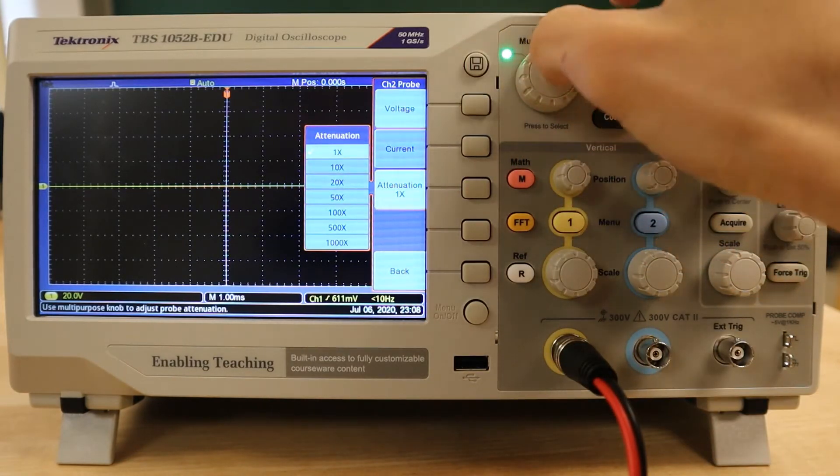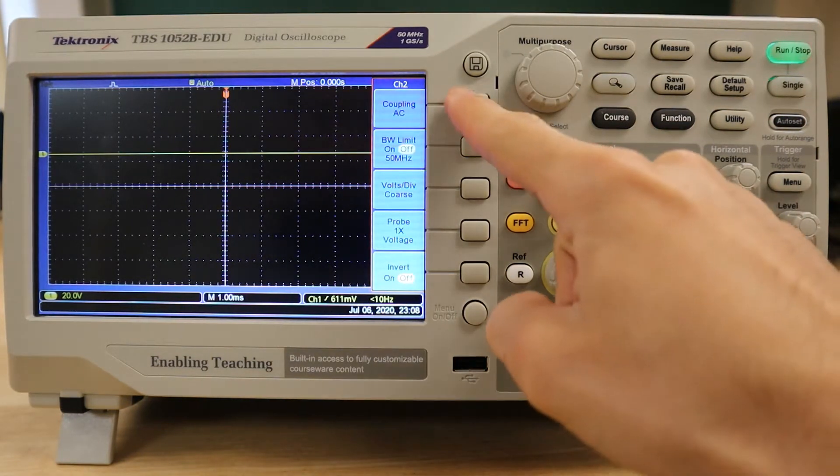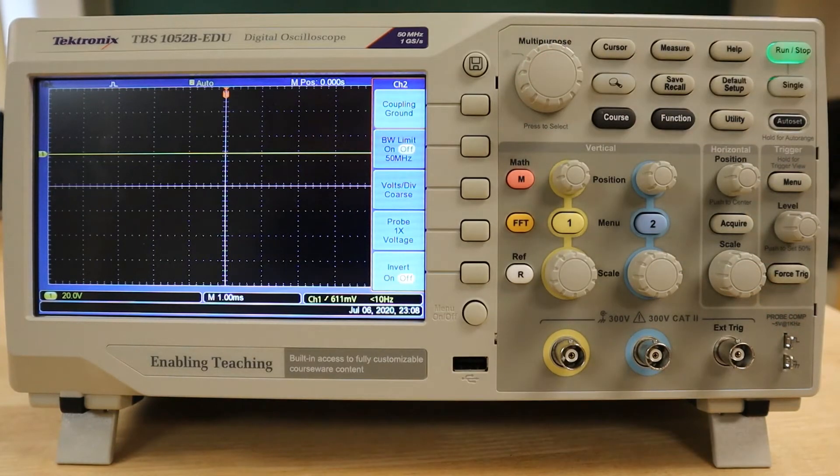Before making any measurements, we also want to make sure the trace is zeroed properly by changing the coupling to ground and adjusting the position of the trace to be aligned with the horizontal axis.